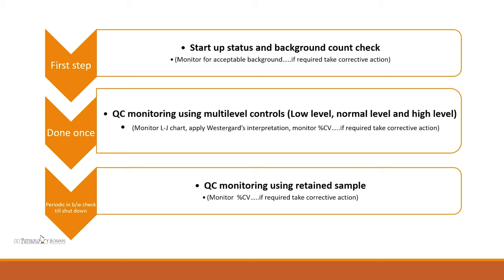Once that is done, we run three multi-level controls: a lower level control, a normal level control, and a high level control. When these samples are run, we monitor them on the LJ chart, apply Westgard interpretation, and monitor the coefficient of variation. If required, we take necessary action. Then QC monitoring continues using retained samples periodically until machine shutdown, and QC monitoring is also done at the end using a retained sample.